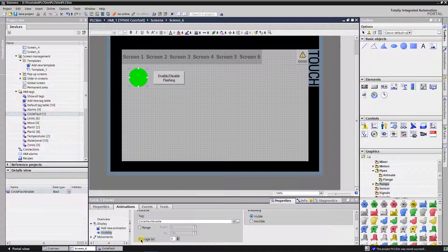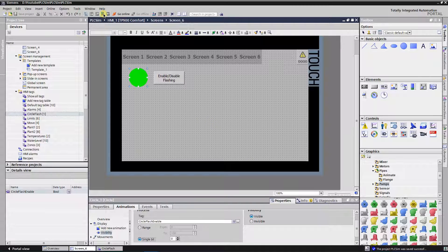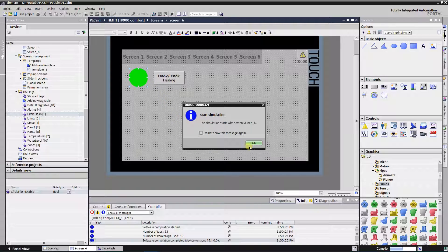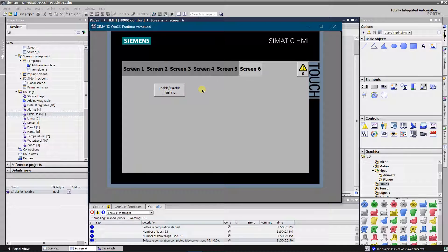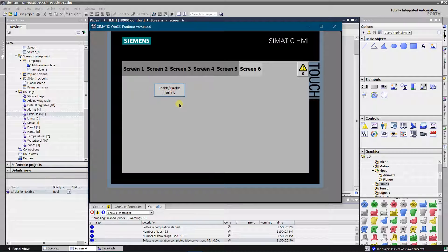Select single bit instead of range. At this point you have a possibility to select when your object will be visible. If you select visible, it means the object is visible when the state of the connected tag is logical 1. If you select invisible, it means your object will be visible while the state of the connected tag is logical 0. In this example I will leave visibility as visible, meaning the object will be visible while the connected tag is logical 1. Let's see the result. At the beginning the circle is not visible, as the tag connected to the visibility property has a value of logical 0. Click the button to invert the state of the tag — now the circle is visible and flashing. Click again and the circle is invisible. Now we have a flashing object with some minor control.